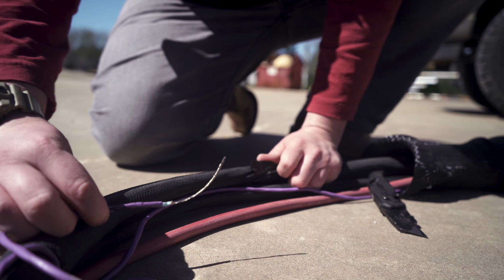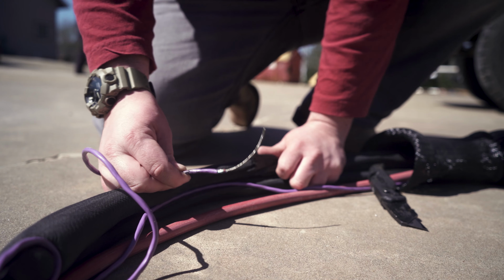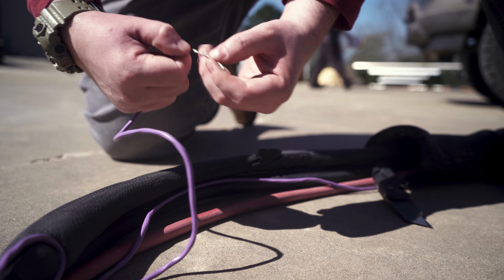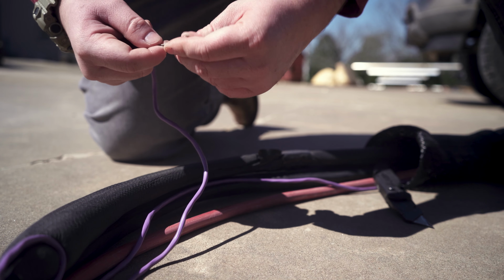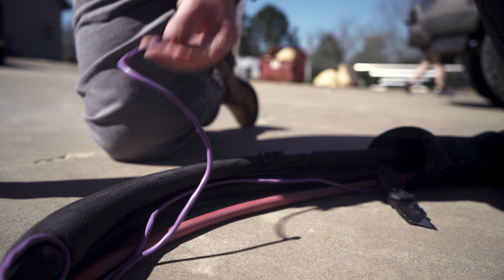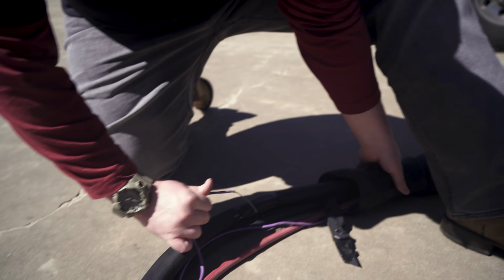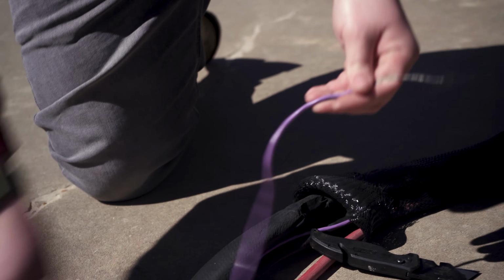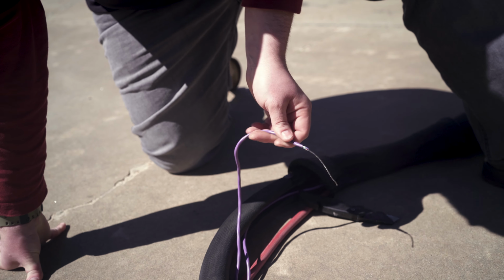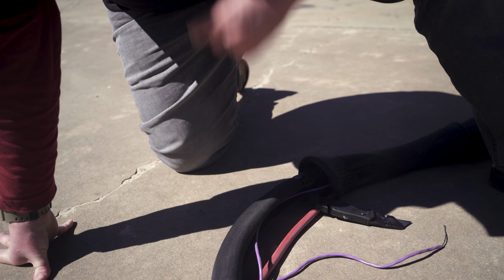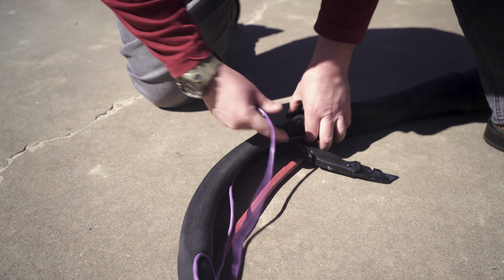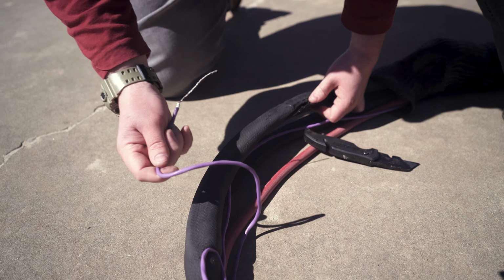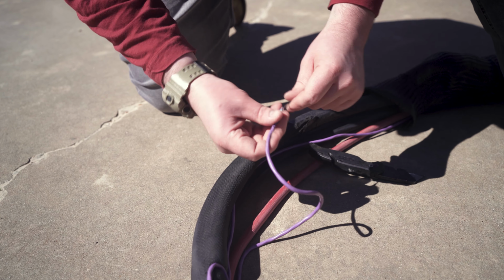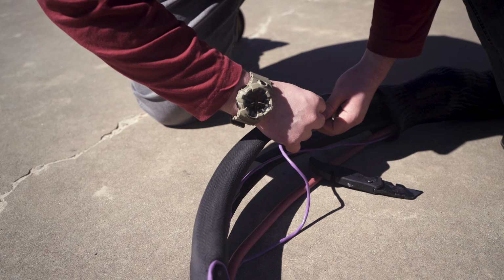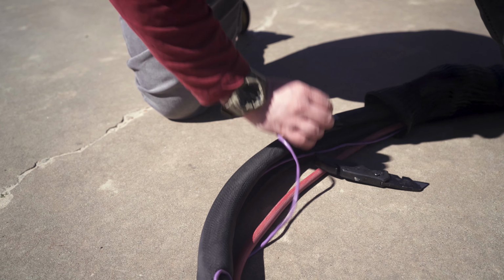But if for some reason this is pulled out and these two strands come apart, your controller will likely read input fail. Or if it just comes untucked and is laying loose inside the scuff assembly, so that it's no longer tucked in against the hose, it's going to be reading more of an ambient temperature, more of an air temperature. And your controller does not know that the hose is already up to temperature, and it's continuing to send power to the hose and will eventually overheat it. So you just want to make sure that this is not untucked. And if it is, you want to make sure that the strands are twisted together well and that the end is inserted back into the hose and secured to the hose very well.